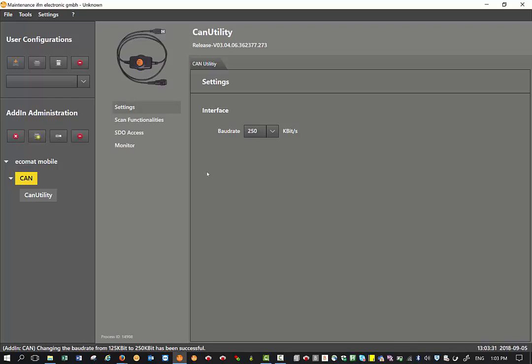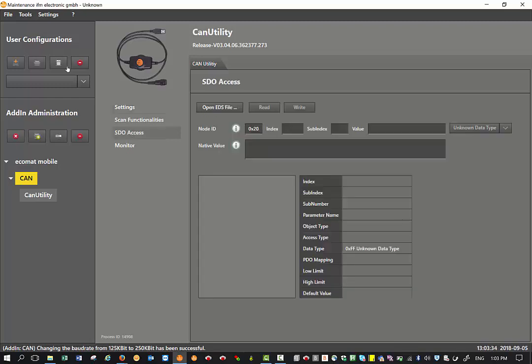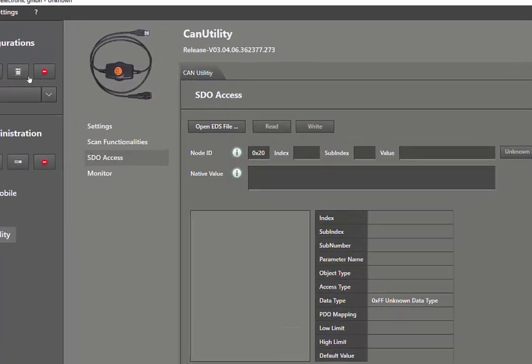And then the next step now is to click on SDO access. In this SDO access, you need to make sure that the node ID matches the node ID of the device you want to configure. In my case, the JN2100 is set up at node ID 11, so this is in decimal.